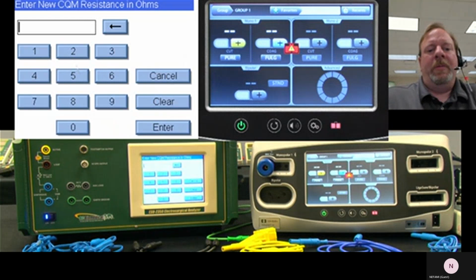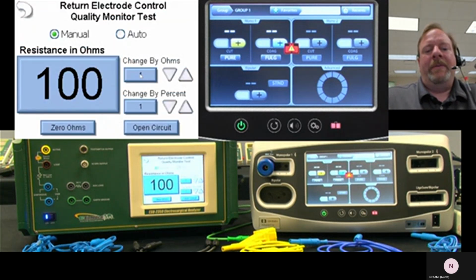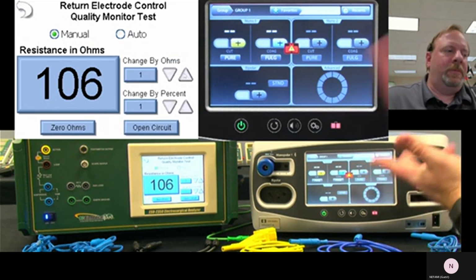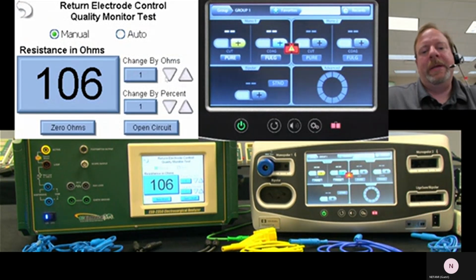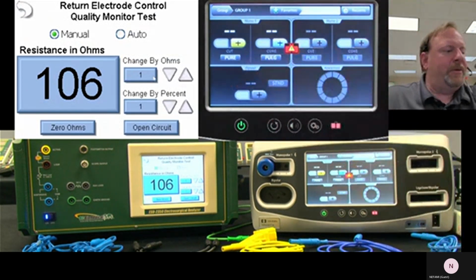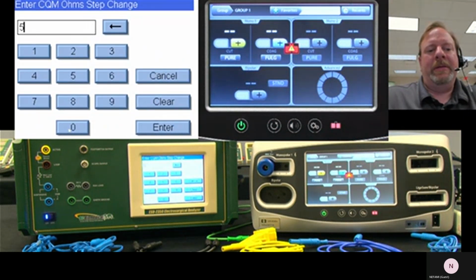In this mode, we can set a resistance. And then we have a lot of the tests that you'll see. They tell you, adjust the resistance slowly, increase it to 135, 140 ohms. Indicate when the alarm triggers or when the alarm goes away. And so we can do that easily here. We can step by 5 ohms.